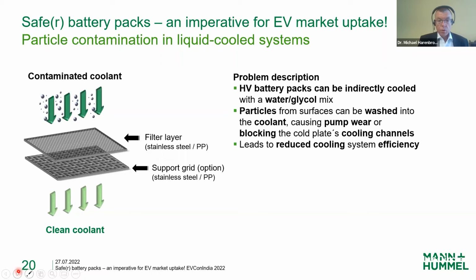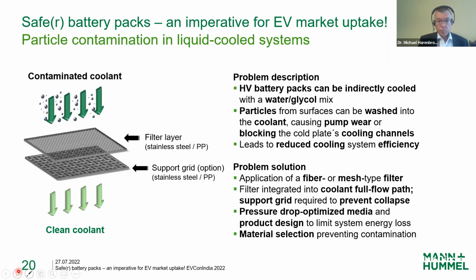But it could also block the cold plate's cooling channels, especially if we are using cooling plates with narrow cooling channels. At the end of the day, this will lead to reduced cooling system efficiency. So what's state of the art for preventing that is to use so-called strainer filters, which would contain fibers or a mesh, placed into the coolant full flow path.